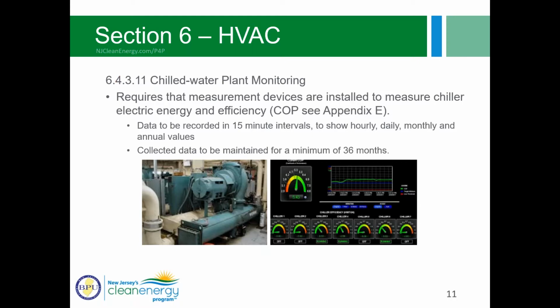All right, so for chilled water plant monitoring. With the chilled water systems, they ask that you measure the performance of the chiller, and you would take this data in 15-minute intervals and be able to summarize it in hourly, daily, monthly, and annual formats. And this would be maintained for a period of 36 months.